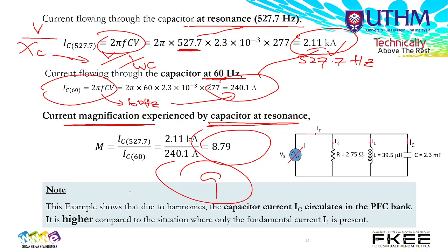So what we can conclude from this example is that due to the harmonics, especially at the resonance frequency, the capacitance current circulating in the power factor capacitor bank is actually higher compared to the situation where only fundamental current is present - 240 amperes fundamental versus almost 9 times higher with harmonic at resonance frequency. That's the effect, and that's how we analyze it.